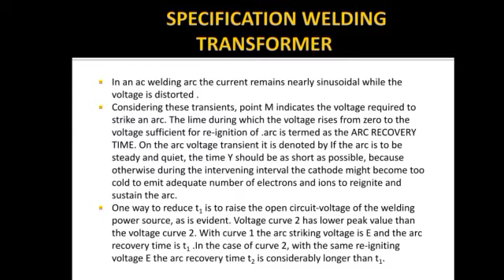One way to reduce T1 is to raise the open circuit voltage of the welding power source. As is evident, voltage curve 2 has a lower peak value than voltage curve 1. The arc striking voltage is E and the arc recovery time is T1. In the case of curve 2 with the same re-ignition voltage E, the arc recovery time T2 is considerably longer than T1.